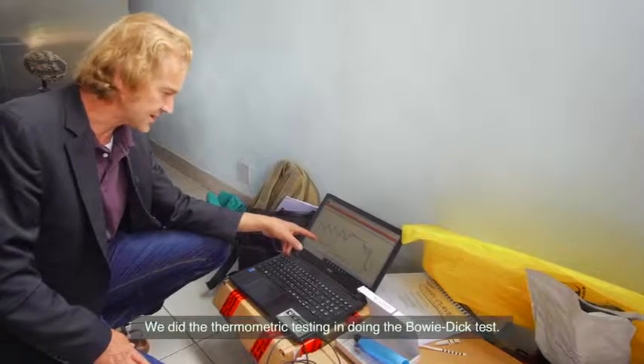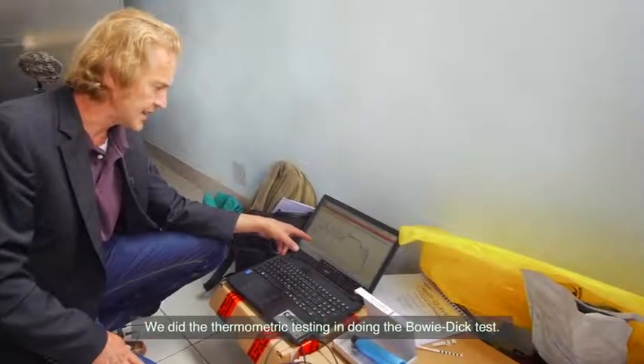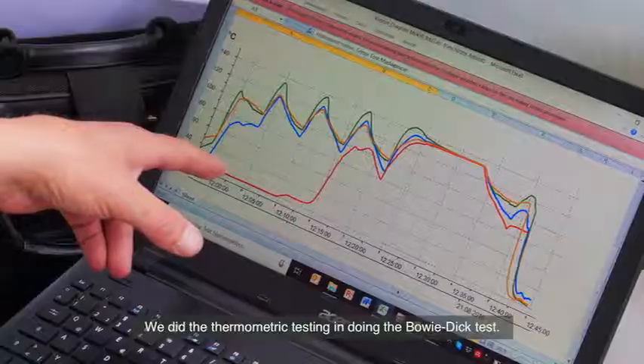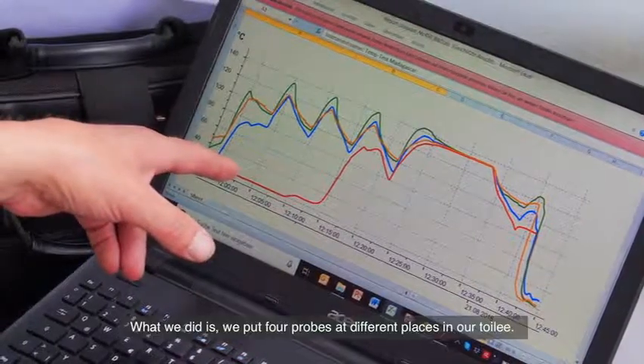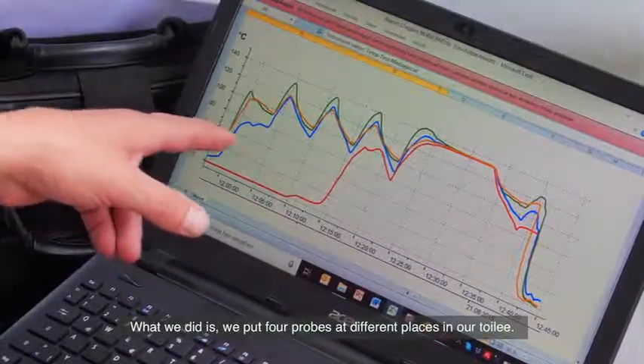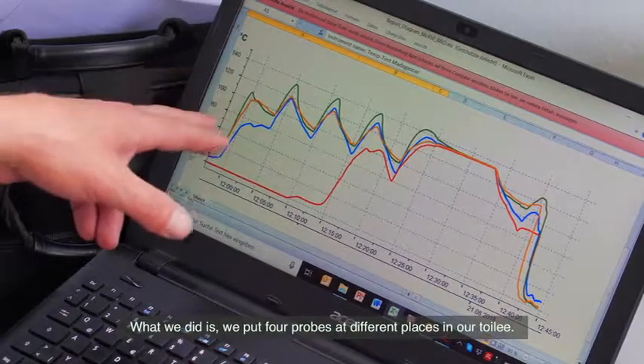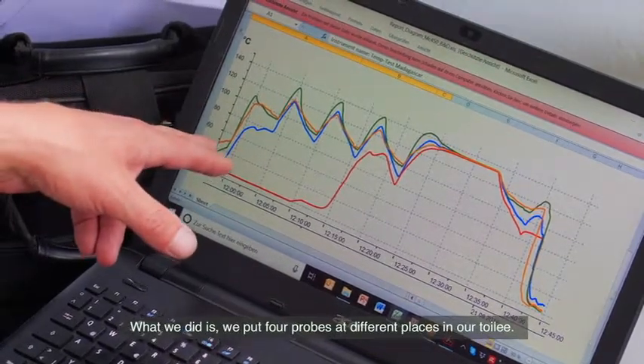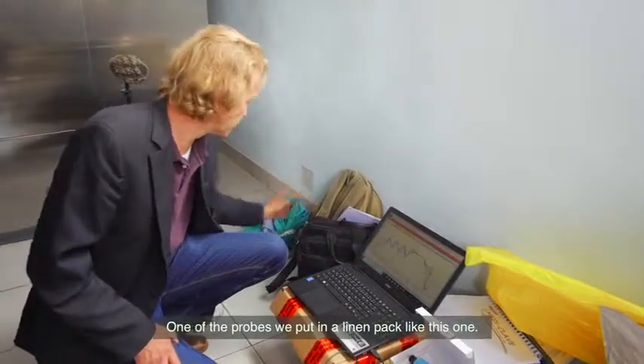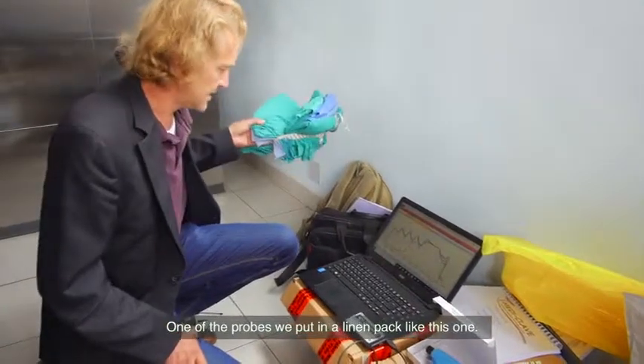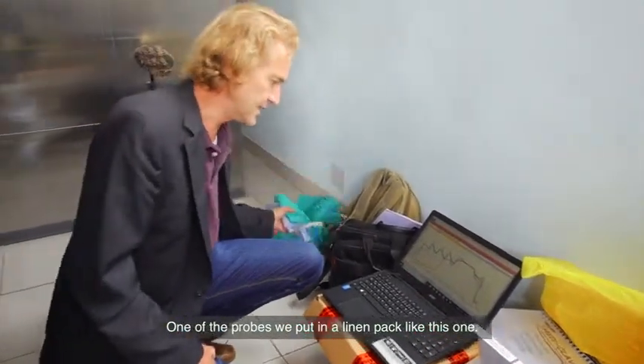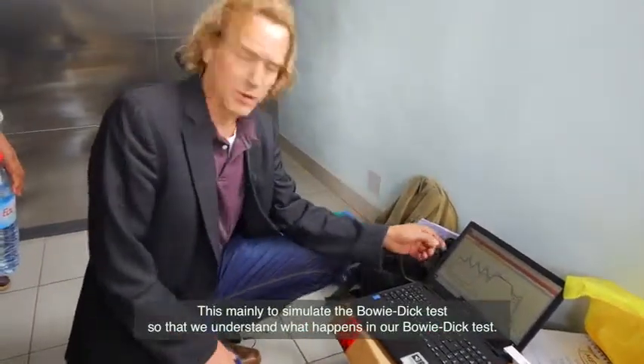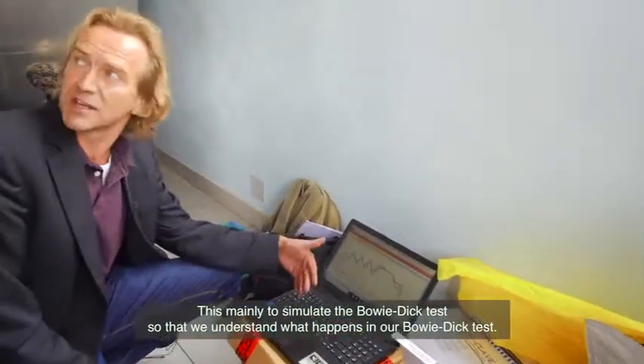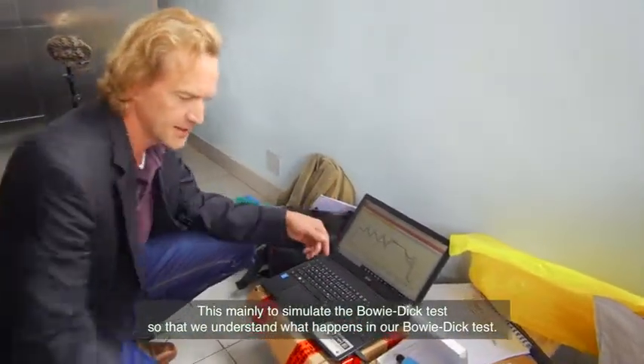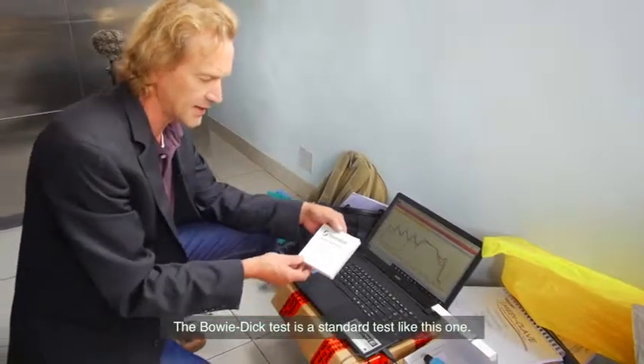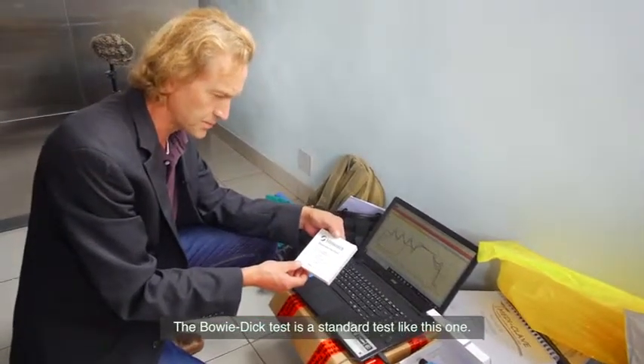We did the thermometric testing during the Bowie-Dick test. What we did is we put 4 probes at different places in our trolley. One of the probes we put in a linen pack like this one. This mainly to simulate the Bowie-Dick test so that we understand what happens in our Bowie-Dick test. So the Bowie-Dick test is a standard test like this one.